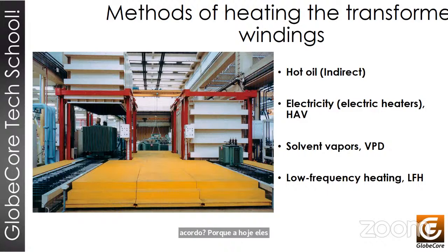So, when selecting the drying mode, it is necessary to proceed from a rational combination of the following: the required quality of dryable material determined by the standard, a class of drying modes that ensures the necessary quality of drying at the specified duration of the process, and the chamber design capable of drying the material according to a certain quality class, without exceeding the mode-specific duration. In addition to the technological features of using one mode or another, the economic aspects, such as the cost effectiveness of using modes of different intensity, should be considered. In order to facilitate the movement of moisture to the surface of materials, it is necessary to ensure fast and good heating of the entire active section of the transformer.